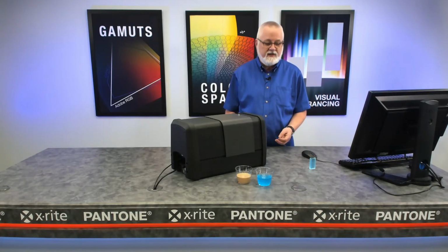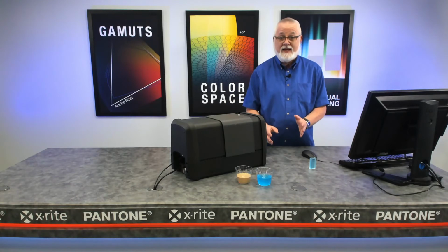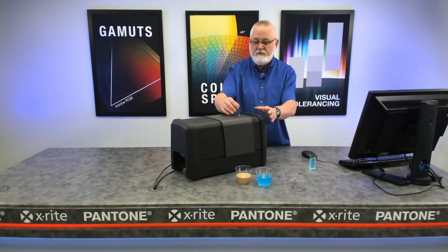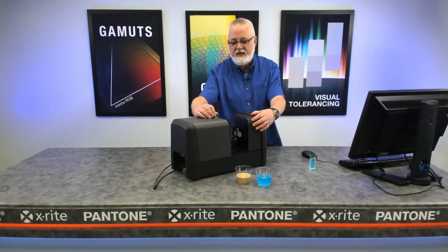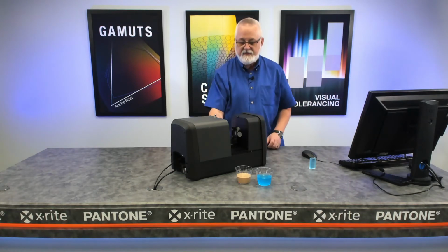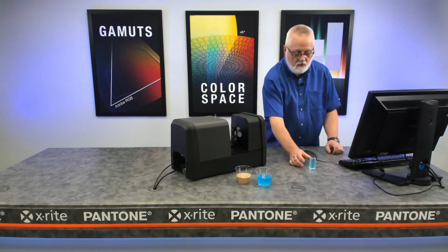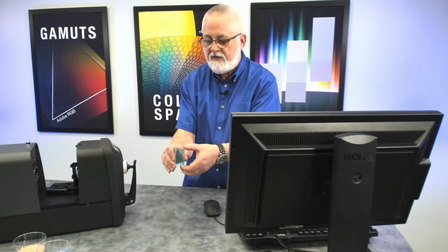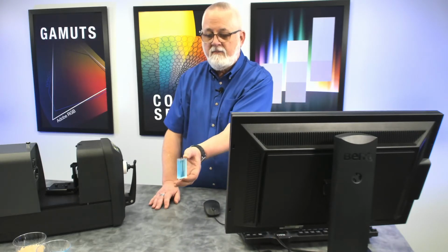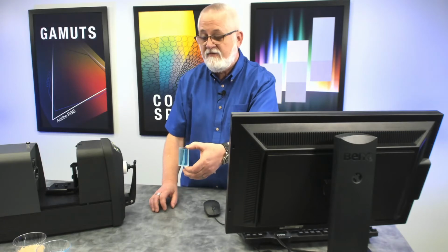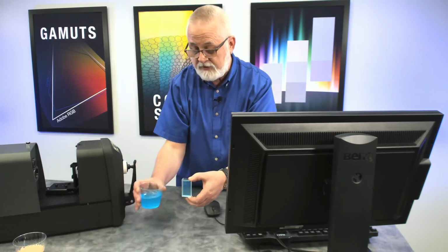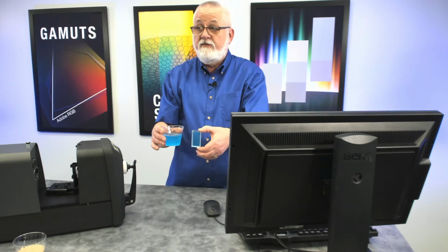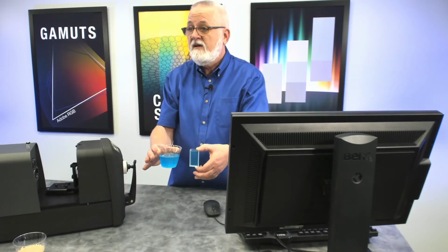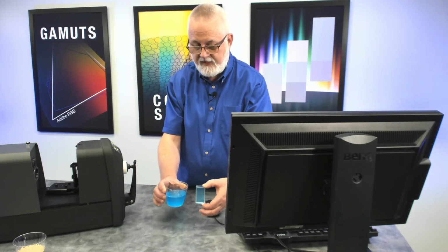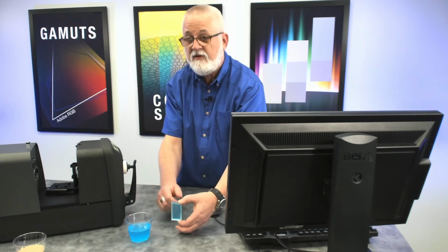So we've measured an opaque liquid that we did with reflectance. Now we're going to look at transmission, and to do that, it's going to involve us opening up the instrument. I'll go ahead and show you that for the transmission chamber. Inside the chamber, we have a holder, and that holder is going to hold this cuvette. Now, the cuvette is a basically rectangular glass piece, and you can see we've poured some of this blue liquid into that cuvette. Now, it looks very different in color, maybe, because of the thickness of that. We're looking through a lot in the glass and a very thin amount here.